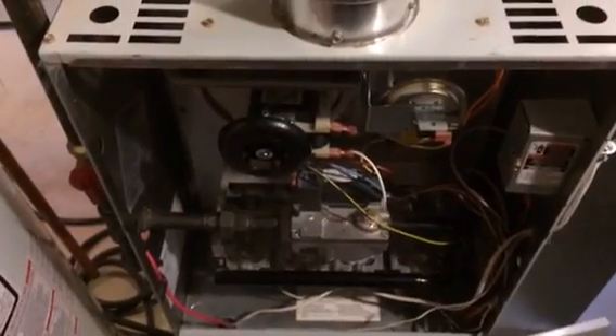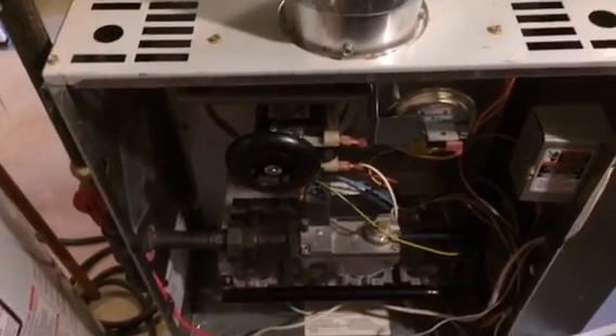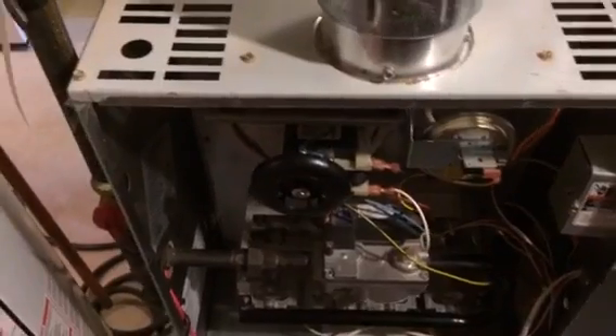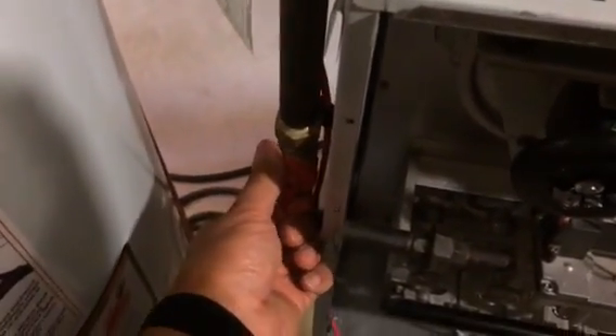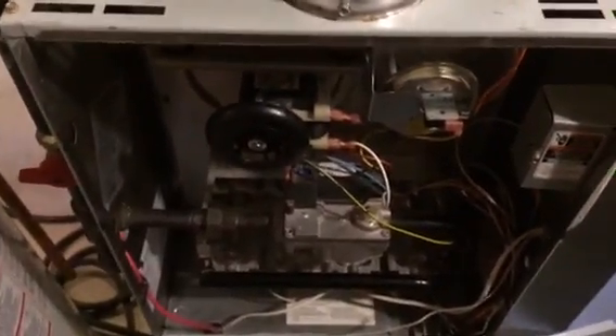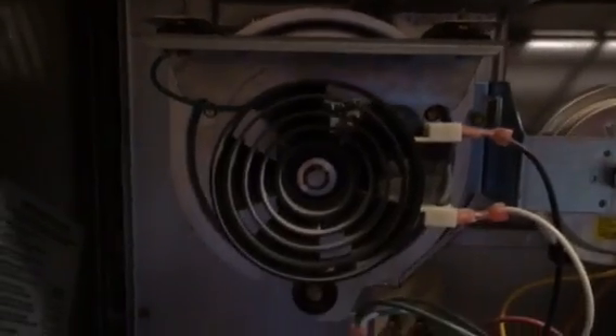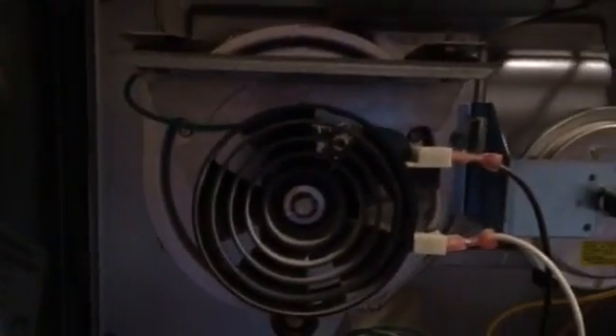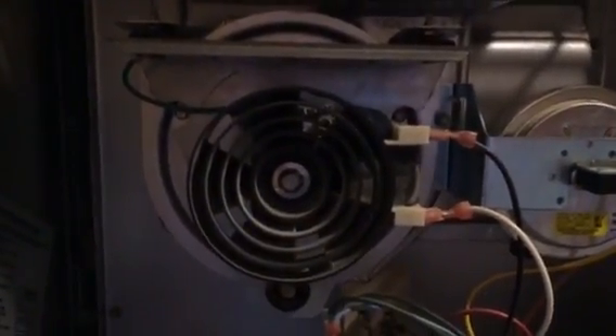As with all appliances, you're going to want to make sure that all energy sources are cut off to the appliance. So we want to shut off our gas and our electrical serving the appliance. Now we are ready to work on this appliance. So as you can see, there look to be 3 screws, one here, and one here, that mount this motor to the furnace. I'm going to remove those screws.